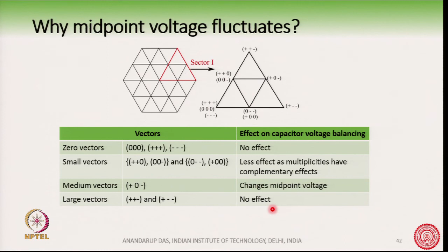Now, apart from that, we have to develop some switching strategies to compensate the midpoint voltage fluctuation. There are many reasons for midpoint voltage fluctuation. One, we saw that if we choose the switching states with the multiplicities, it causes the midpoint voltage to fluctuate, as we had just explained. But unbalanced 3-phase operation can also cause it, and there may also be capacitor manufacturing tolerances, non-idealities in the capacitor, or certain sudden deviation of capacitor voltage due to some unforeseen circumstances. If those things happen, the midpoint voltage may suddenly go away from the 0 potential which we had throughout assumed.